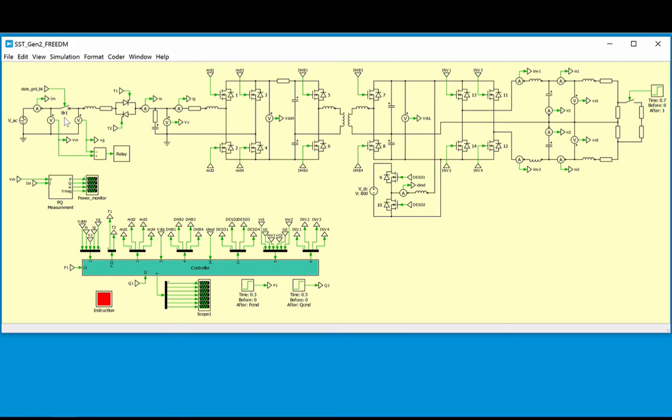Moving from left to right, I will briefly discuss the rest of the circuit. The first converter stage is referred to as an active front end, whose purpose is rectification. The four MOSFETs here are switching at 12 kHz, and the output of the H-bridge is connected to a 12 kV DC link.